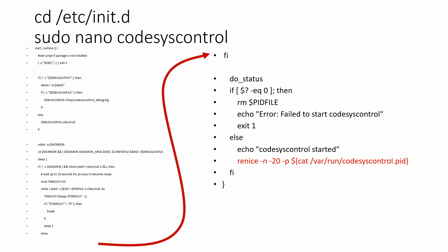Now, this next part is maybe not needed — frankly, I don't see any benefit in my setup — but if you run anything on your Raspberry Pi besides CODESYS, this can come in handy. It's about increasing the niceness of your CODESYS control, which puts it at a slightly higher execution priority and can influence jitter when your task is executed.